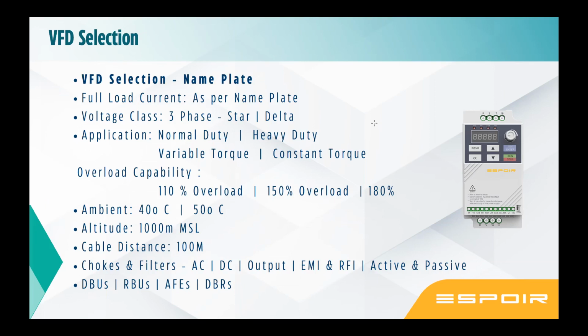If it is above 100 meter, there are filters you need to consider. There are filters like output filters, but again you need to decide based on the zone. You need to probably put 2, 3, 4 different chokes at different locations. One is closer to the drive, one is closer to the motor. As distance grows, the selection of the filter also changes. Then the VFD also you need to consider. So this is a very complex selection. We need to work based on the application.